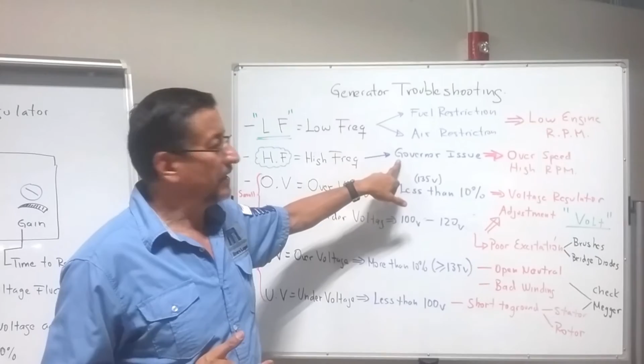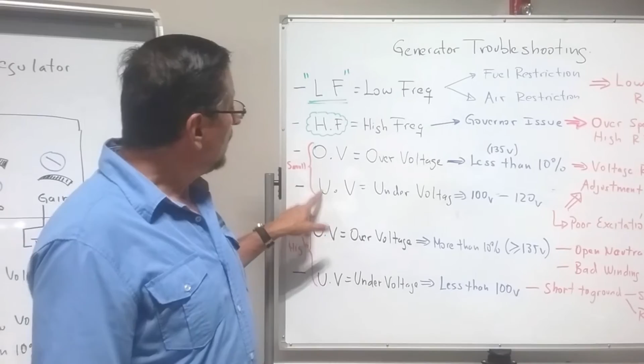This is a typical fuel injection pump, a rotary pump, and this is the governor and this is the fuel injection pump. A mechanical problem on the governor means the handle stays higher or lower and the RPMs increase or decrease. Mechanical problems on the governor normally produce high frequency or overspeed. Another common problem is overvoltage or undervoltage.